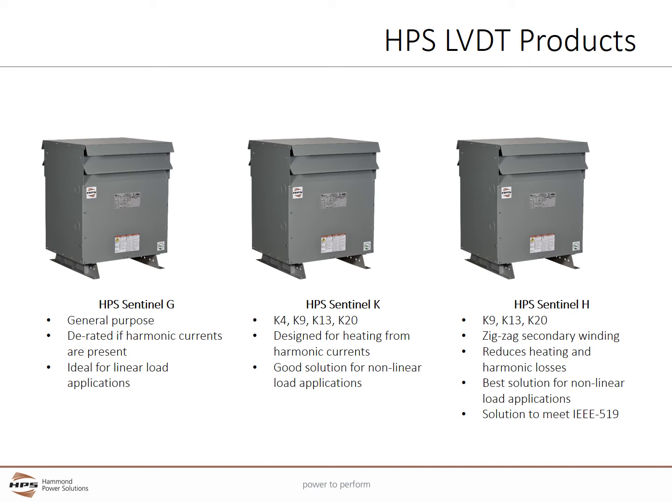The HPS Sentinel-K is K-rated in the ratings of K4, K9, K13, and K20. The more harmonics present, the higher the K rating specified. It is designed to handle the additional heating from harmonic currents. Harmonic currents are generated by non-linear loads where AC is converted to DC power. It is a good solution to power non-linear load applications.